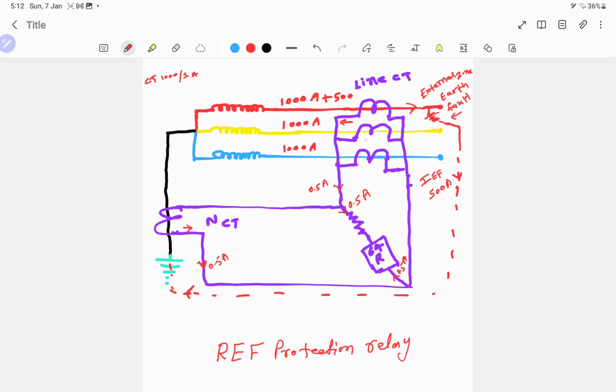So here the three CTs are attached with the line. So it's called line CT, and they measure the current for protection purpose. And there's one more CT here which is called neutral CT.